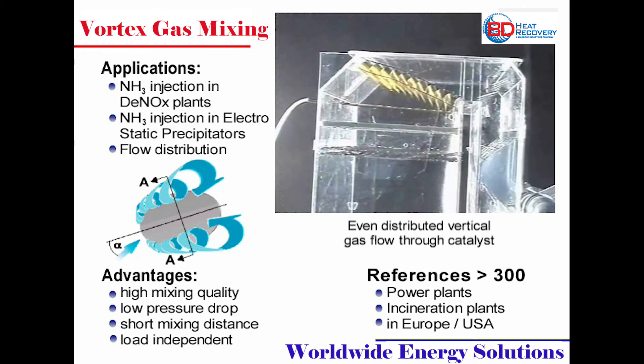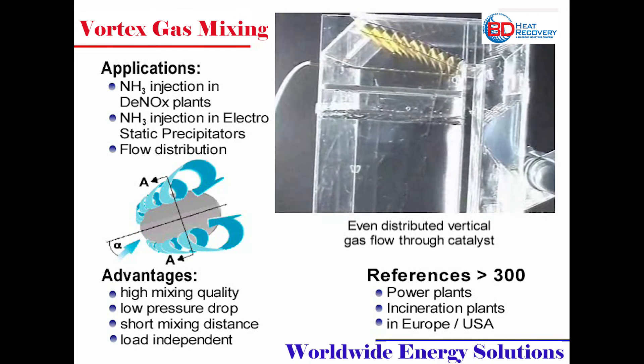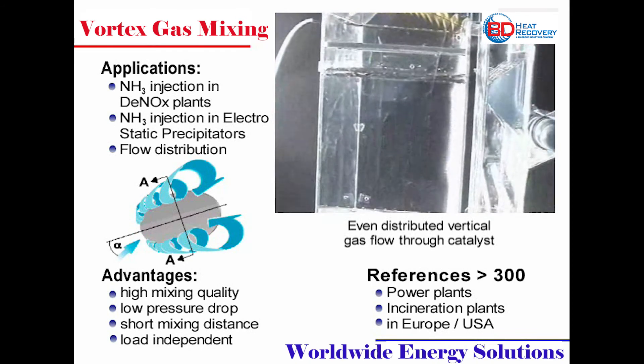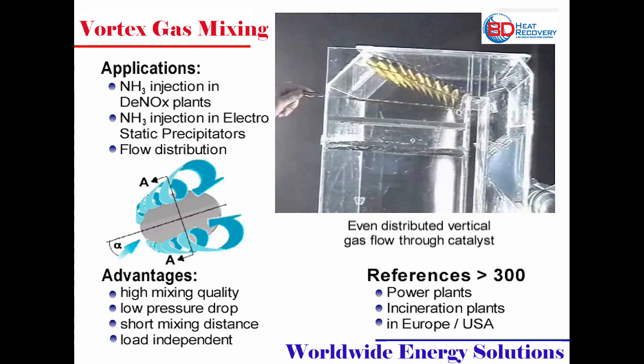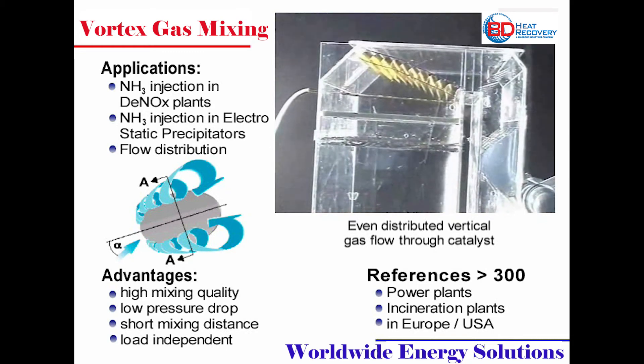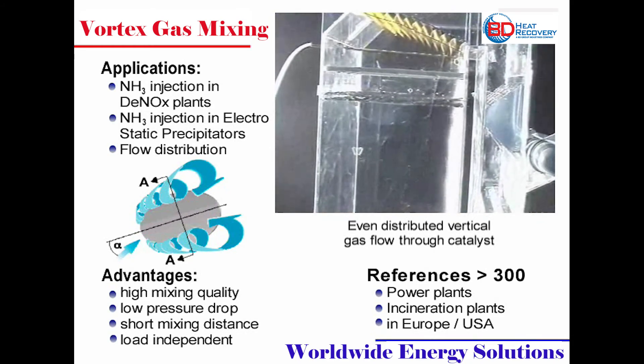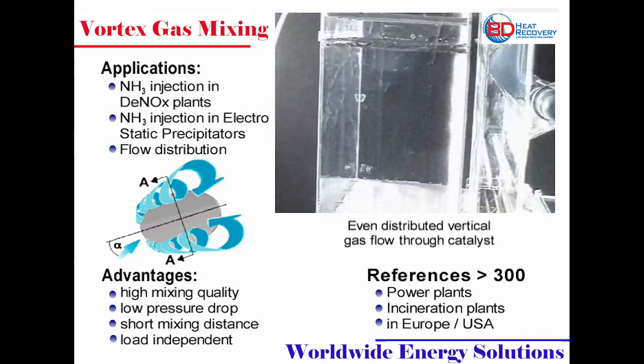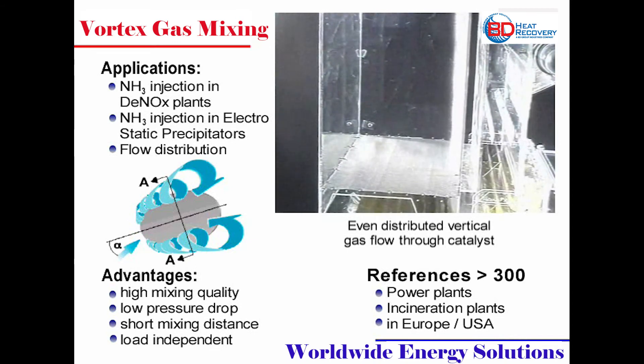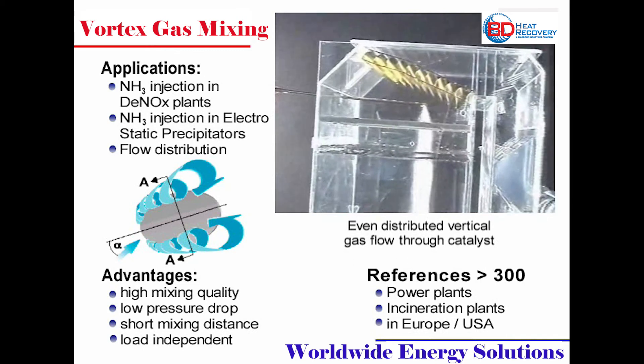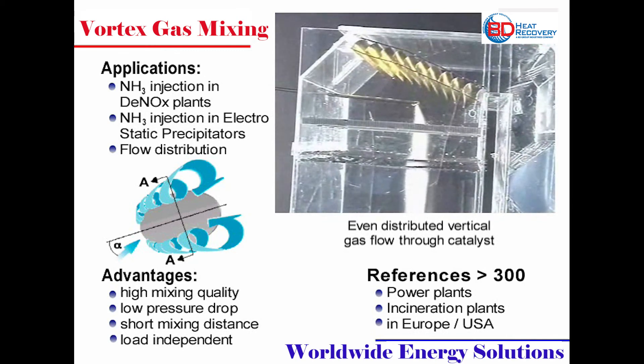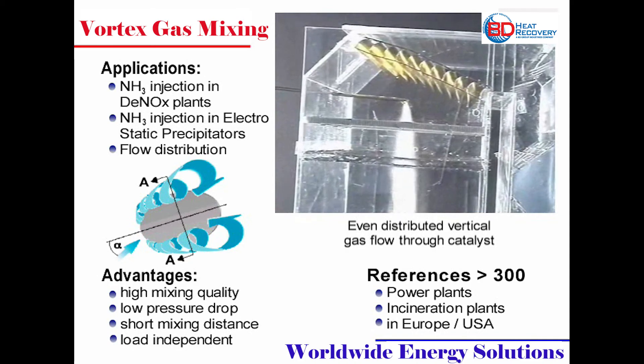This results in particle flows being mixed thoroughly before they reach the catalyst surface. The quality of the mixture and the straight flow through the catalyst and the subsequent ductwork is visualized by injection of an oil fog into the main stream. This indicates the high performance of a well designed set of static gas mixers, homogenizers and guide vanes in order to achieve evenly distributed gas flows.